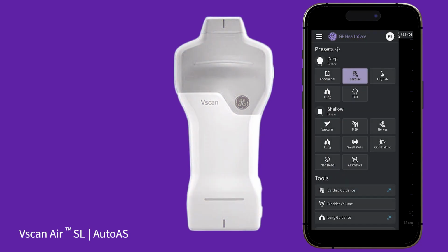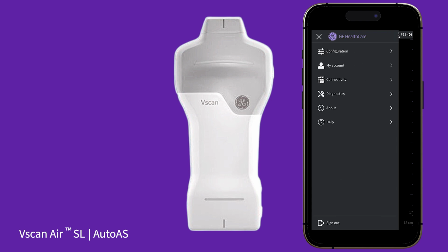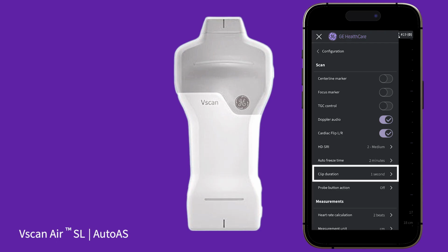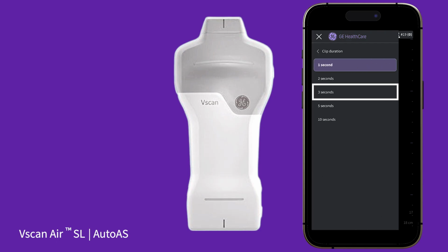Use your Vscan Air SL to acquire standard 2D cardiac images, with the sector transducer, and with either the cardiac preset or cardiac guidance. Before we start scanning with the cardiac preset, be sure to configure the clip length to at least 2 seconds for the AutoAS evaluation. Swipe right, select the menu icon, tap Configuration, tap Clip Duration, and tap 3 seconds.